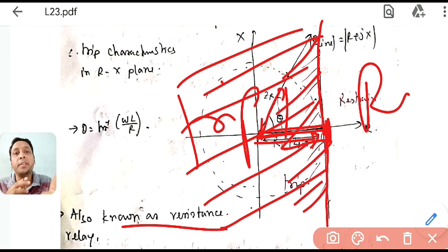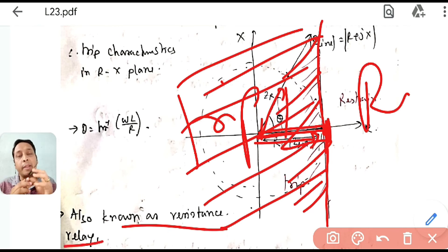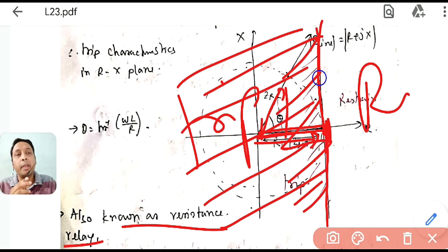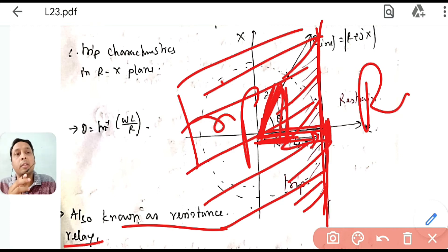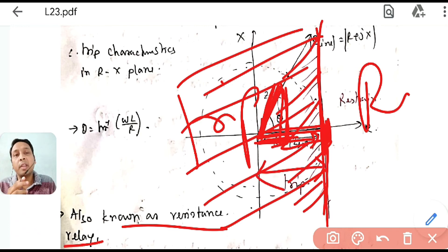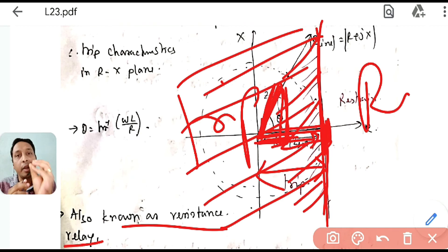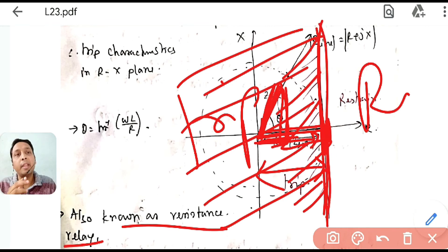This relay is also known as a resistance relay, because it compares only the resistance component. Generic impedance relay is named 'generic' because changing the value of τ gives different relay types. When τ = 0, ZR·cosθ = R, and the relay compares only R against Z_set, making the trip boundary a line perpendicular to the R-axis.